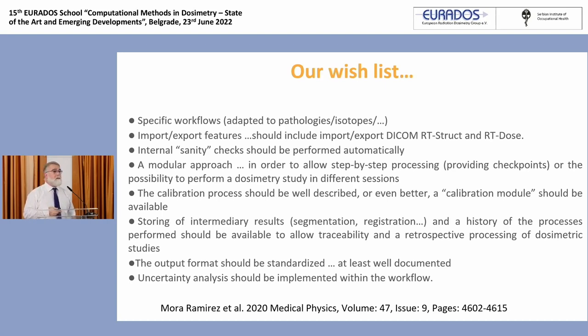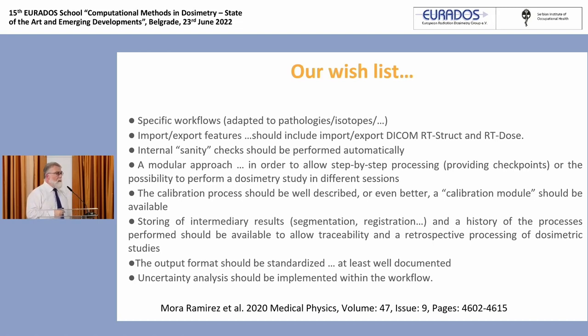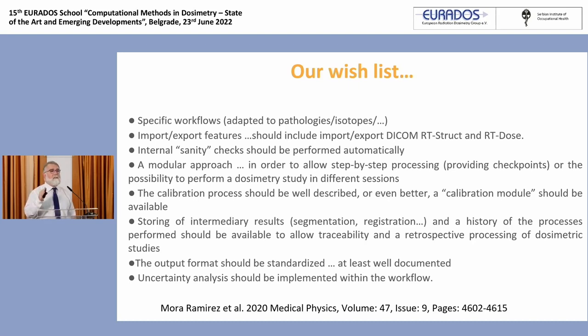We need import-export features — we don't want to be limited as was the case with the dosimetry toolkit in the first version. When you start the process, you have to be able to finish it. If someone interrupts you, it means you've lost everything you've done. We want internal sanity checks — very little addressed currently. Whenever you are importing data from another department, half of a physicist's time is spent just making sure the data is correct. We want to know if the acquisition time, collimator selected, and matrix size are the same for all time points — these can be integrated in software with warning flags.